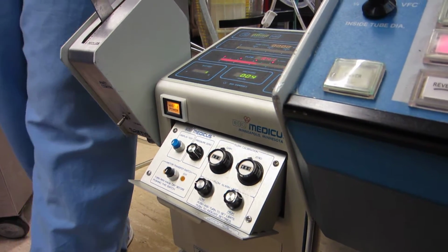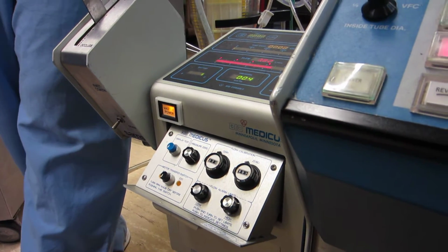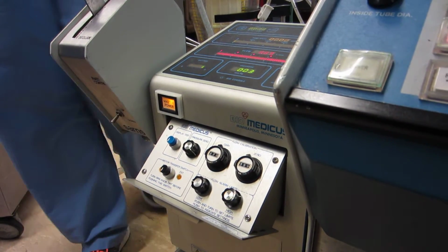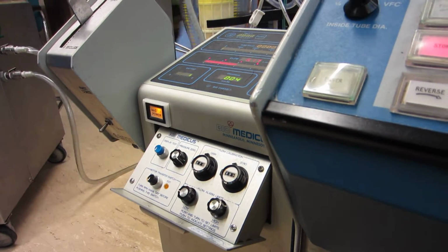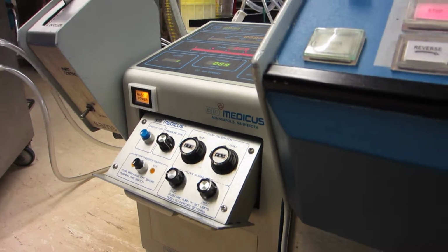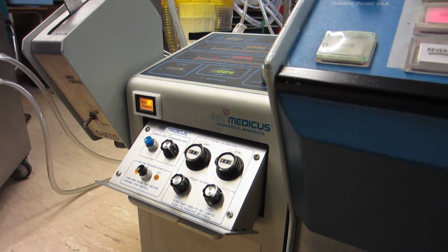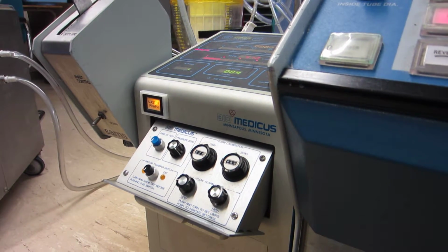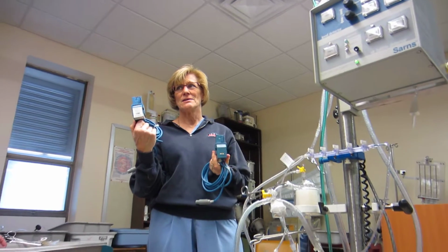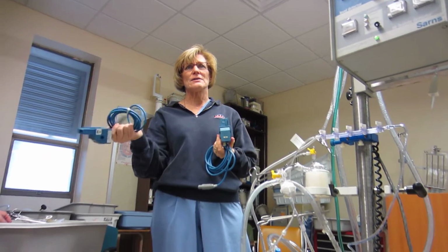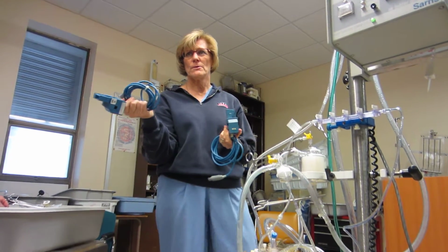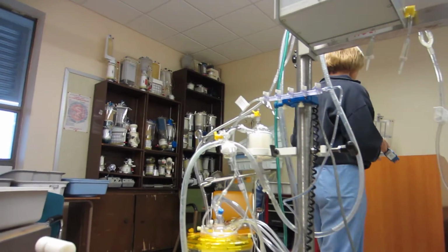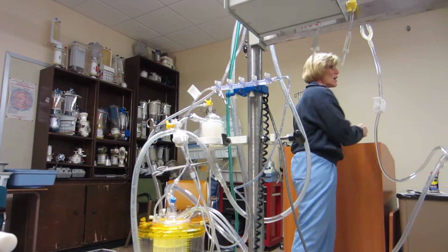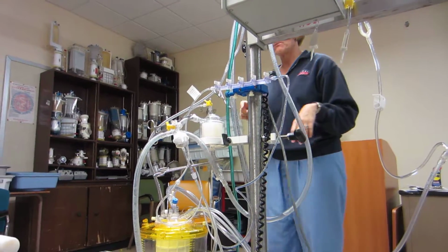Did I have that right? No. You're going to set the gain. The gain is specific for the flow probe. So like if you look at the other two flow probes I have in here, because if I can't get that 550 to work, I've got another 540 pump, so I took out a couple more flow probes. This one's 610. This one's 380. So the gain is specific for the flow probe. And then once you have the gain set, you can set the zero.